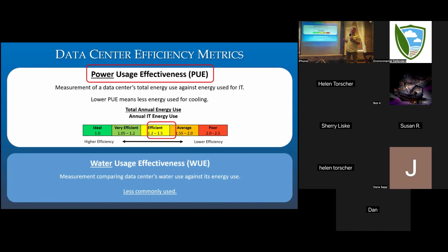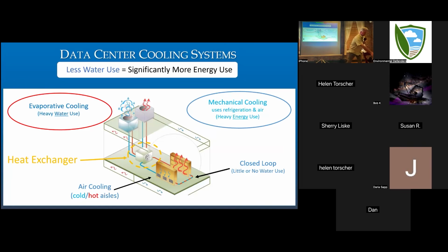One of the things data centers are trying to do is use as little energy as possible, because that's where the real cost of operations is. So they want any energy they're using to go directly to the IT. One other thing I want to point out: there is a direct correlation between the efficiency of the cooling system and water use. The more water efficient the system is, the more energy intensive it is. The less water efficient it is, the lower the energy use. There's a direct correlation there. So there is an incentive for them to use the most water consumptive technologies possible, because it will lower their energy costs.